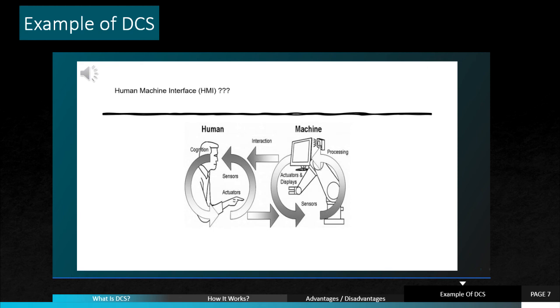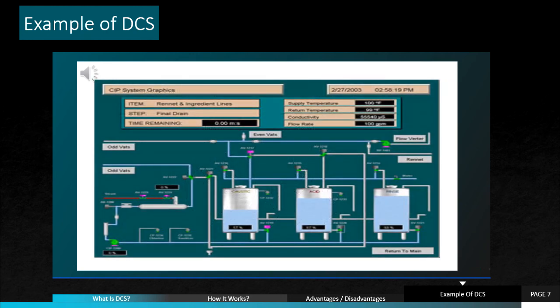So what is a human-machine interface, HMI? In a DCS system, HMI is used to help operators control and monitor machines by using touchscreens that are connected to the machine. An example of HMI that we usually use is an ATM machine. When we touch the screen, the machine will start to work. Okay, this is an example of an HMI screen. It is really useful for the operator since they can see what is happening in the production. They can see the level of the water inside the tank and the temperature inside the tank just by using HMI.